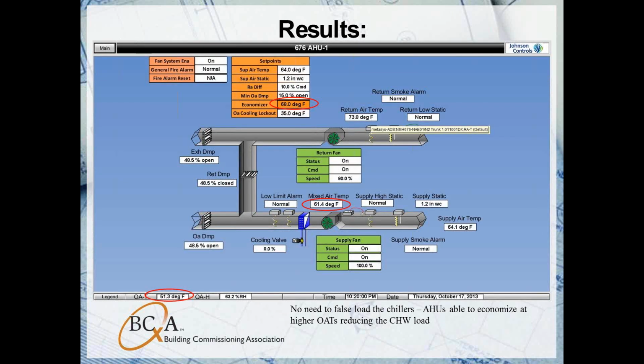So some results we saw on the air handler side: now that the chiller plant is able to function more efficiently at part load, we no longer need to false load our chillers by locking out economizer mode. So we've set our economizer lockout temp at a fairly high 68 degrees. And you can see we're at an outside air temperature of 51 degrees, perfect economizer weather, and we're very effectively meeting our supply air temperature set point here, 64 degrees, not using any mechanical cooling here.